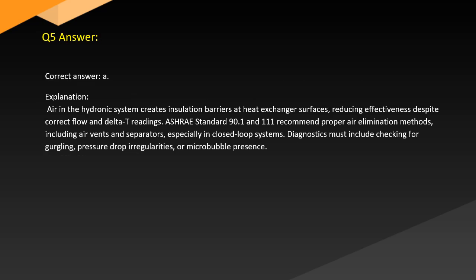Answer. Correct answer A. Explanation. Air in the hydronic system creates insulation barriers at heat exchanger surfaces, reducing effectiveness despite correct flow and delta T readings. ASHRAE Standards 90.1 and 111 recommend proper air elimination methods, including air vents and separators, especially in closed-loop systems. Diagnostics must include checking for gurgling, pressure drop irregularities, or microbubble presence.